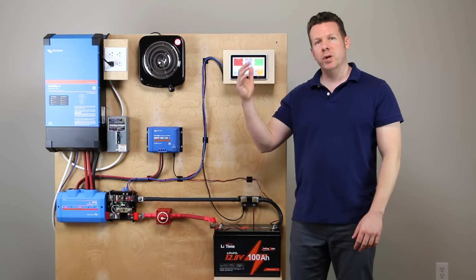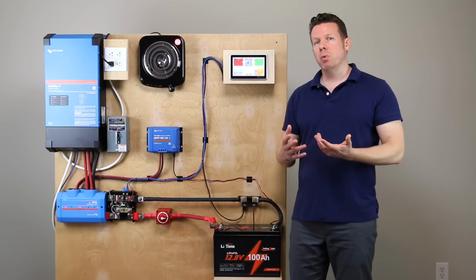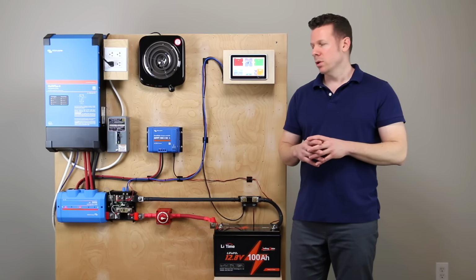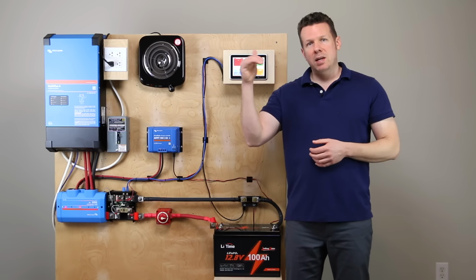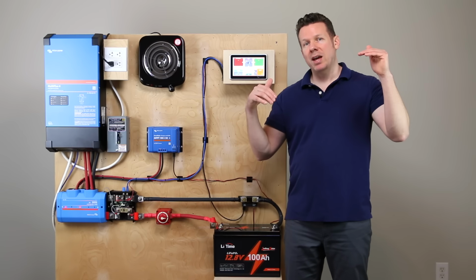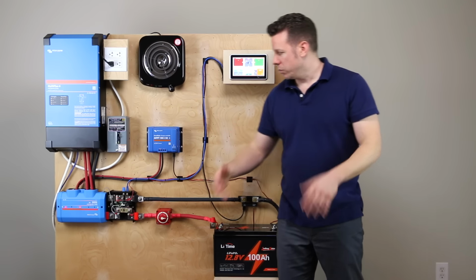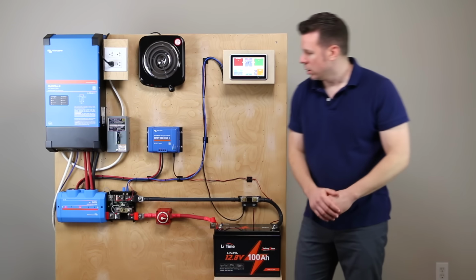So if you do a 48 volt battery system, you would want to go with a class T fuse. And those go up to 80 volts and a maximum of 800 amps. So that's what you would use for your main system fuse.